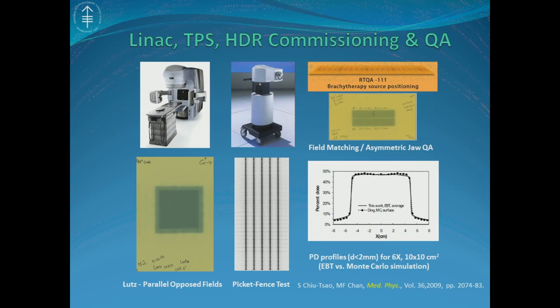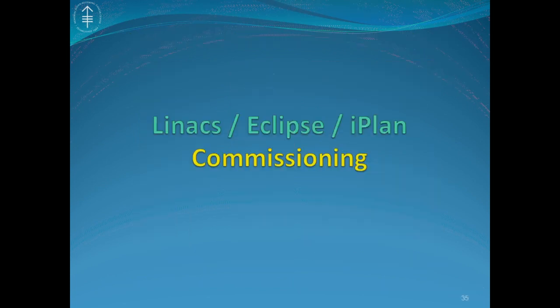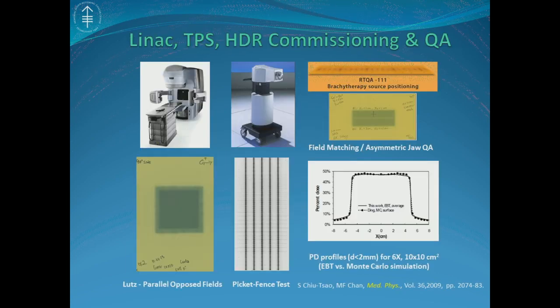Now I will show you some clinical examples of film applications, such as treatment machine and planning system commissioning. Here are some LINAC QA films and a source positioning verification film. And for research, you can even measure a surface dose profile at a very shallow depth, such as less than 2 millimeters.